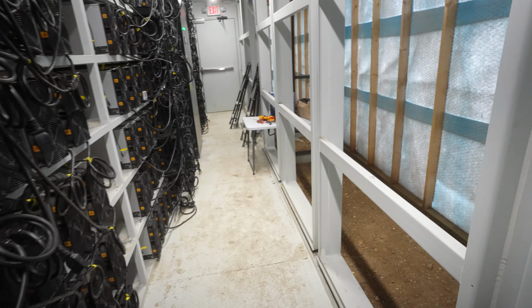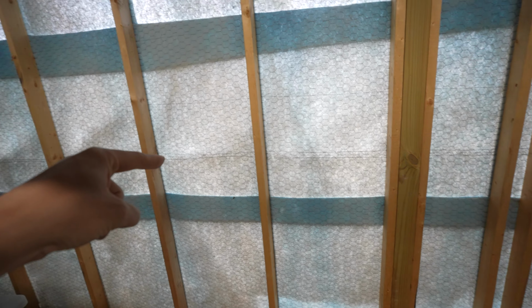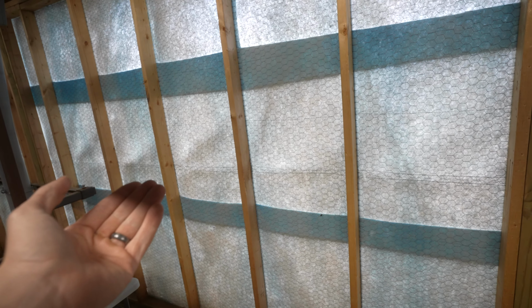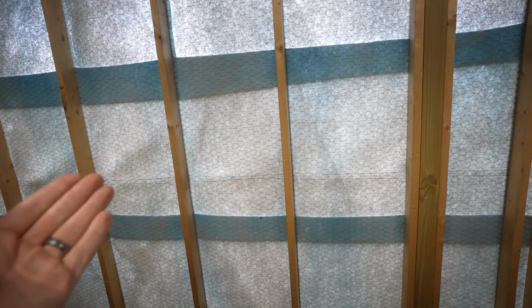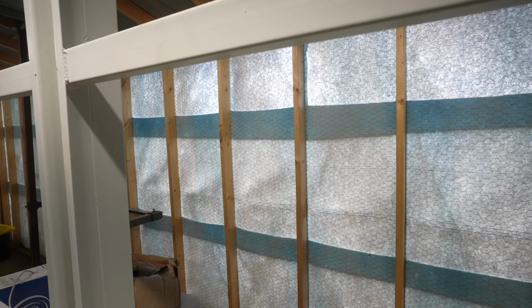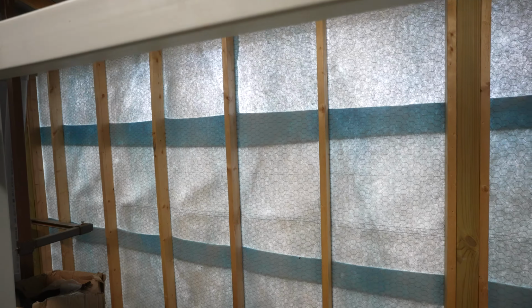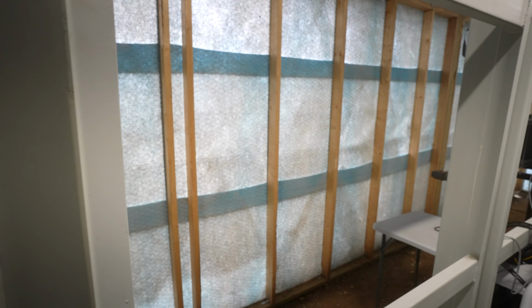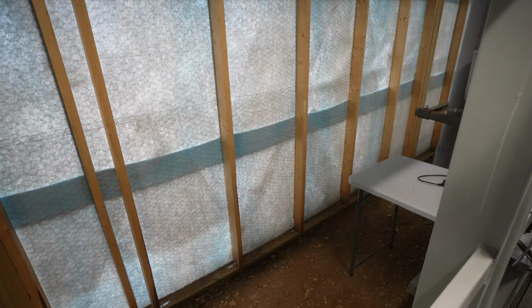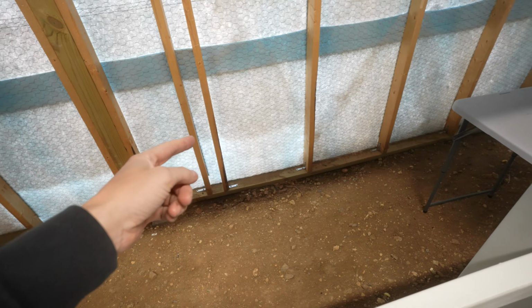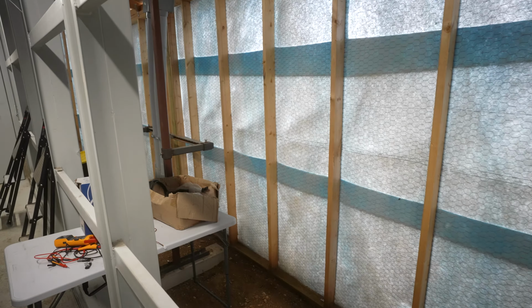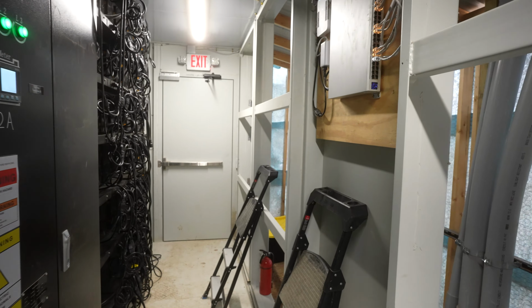You can see how we set up our filtration system here. We've got nice filtered air coming in, with that blue polyester filter. It's got chicken wire to make sure the filter does not rip. In North Dakota it gets very windy, so we had to put in chicken wire to make sure the wind does not rip the filter. All of it is held down by beams and brackets, so it's all nice and sturdy.